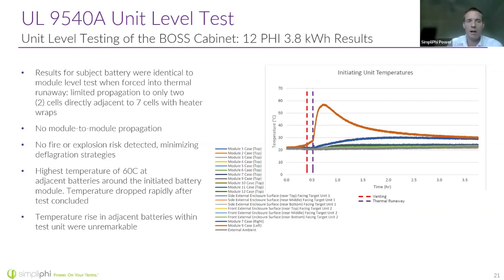Not only that, but the highest temperature of the adjacent batteries, outside of the battery that was forced to go through an off-gassing event, was only 60 degrees Celsius. And after we concluded the test and turned the heaters off, the temperature rapidly dropped. So again, this is really showing you that there's some safety here. This is not a certification, just a test, but it's showing you that it was really kind of an unremarkable test.